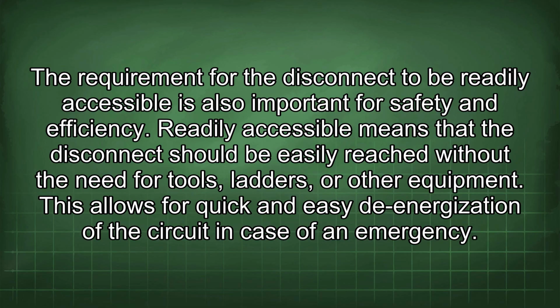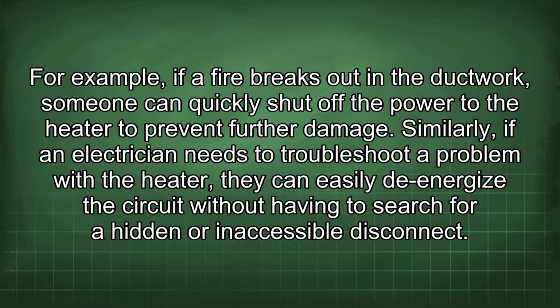The requirement for the disconnect to be readily accessible is also important for safety and efficiency. Readily accessible means that the disconnect should be easily reached without the need for tools, ladders, or other equipment. This allows for quick and easy de-energization of the circuit in case of an emergency. For example, if a fire breaks out in the ductwork, someone can quickly shut off the power to the heater to prevent further damage. Similarly, if an electrician needs to troubleshoot a problem with the heater, they can easily de-energize the circuit without having to search for a hidden or inaccessible disconnect.